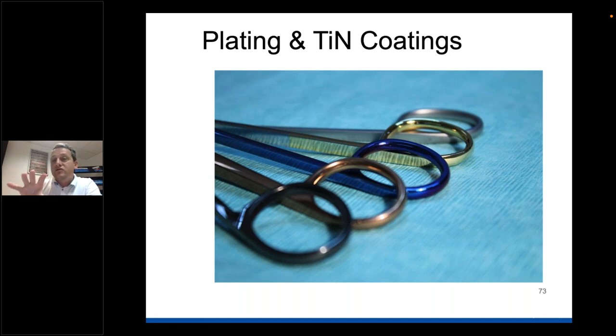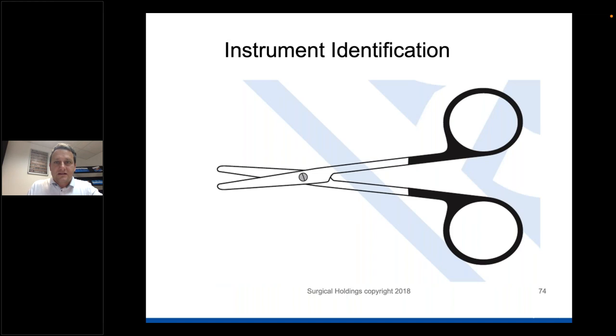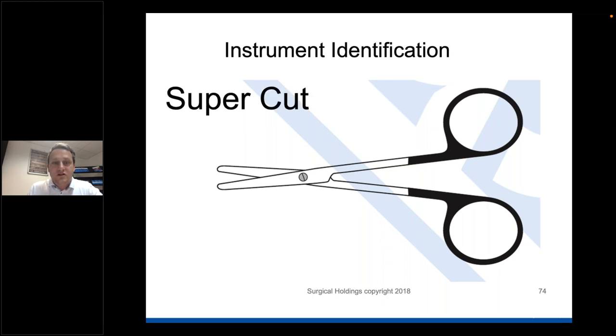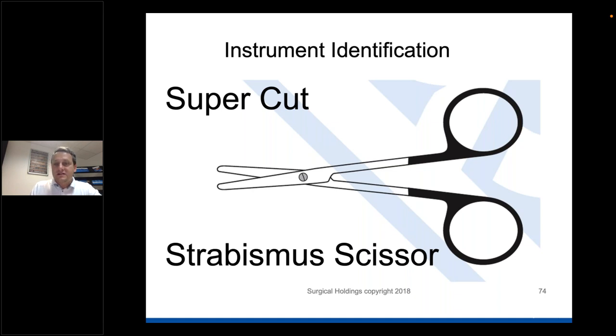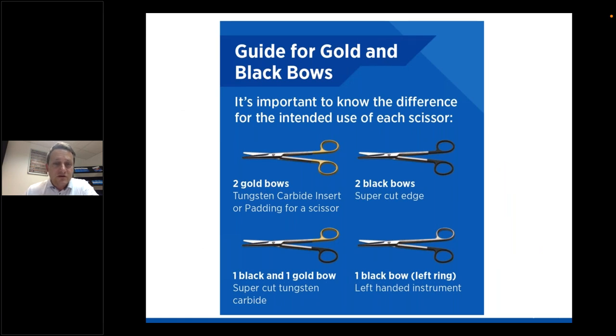Some blue surgical instruments will be titanium and are okay to be dyed blue, but generally you'll see gold and black coatings. On scissors, two black bows designate a supercut strabismus scissor. These black bows use a different chemical process - not as robust as titanium nitride, so you may get scratches, as they're there only for identification. Two gold bows on needle holders generally means there's a tungsten carbide insert - the same coding can appear on scissors. One black, one gold means supercut tungsten carbide.